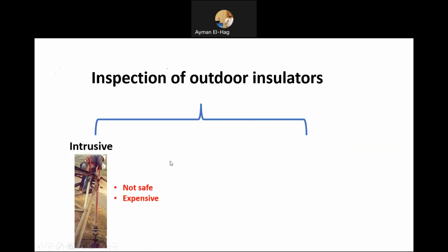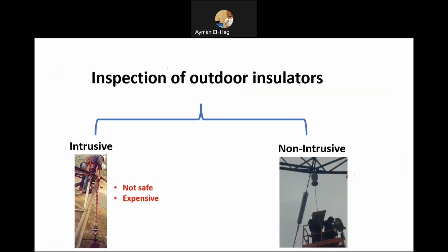The other category of inspection is non-intrusive. Non-intrusive in the sense that you do not need to shut down the line, and also you are not in physical contact with the high voltage lines. You use certain types of sensors that you can have at a safe distance from the conductors. As you can see here, this is basically an RF antenna, and this is an outdoor insulator. We are doing the inspection of any damages using the RF antenna. So you do not shut down the line, and you are safe with respect to your location relative to the insulator.